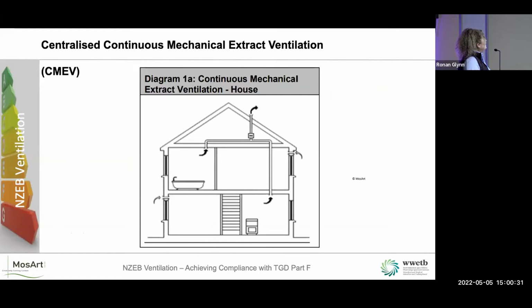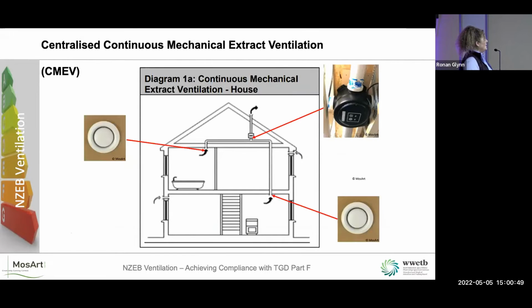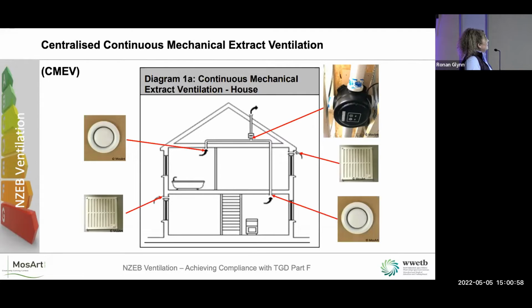This is CMEV, which is centralized continuous mechanical extract ventilation. Instead of having intermittent extract vents in our bathrooms and all of our wet rooms, now we have one centralized fan in the attic, and that extracts from all of the wet rooms continuously, 365 days of the year, nonstop. As the fan pulls the air out through the dwelling, it creates a negative pressure, and the air naturally spills in through the background ventilators to fill that void.